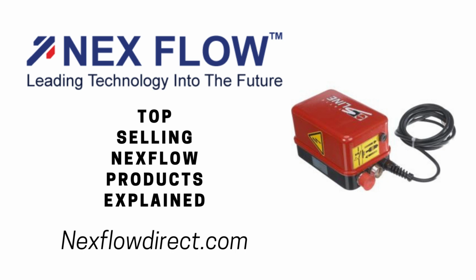Many power supply connections have a plastic bayonet-type connection. What's interesting is that the plastic over time will be affected by the ionization of the air in the area, and it can become very brittle and break, again causing a failure to the power supply and requiring a replacement.